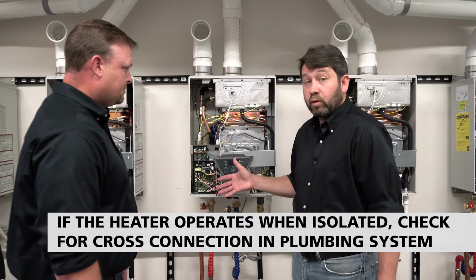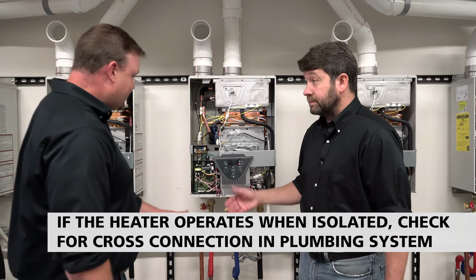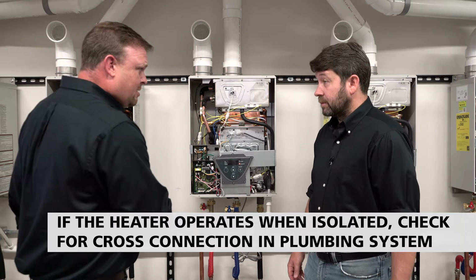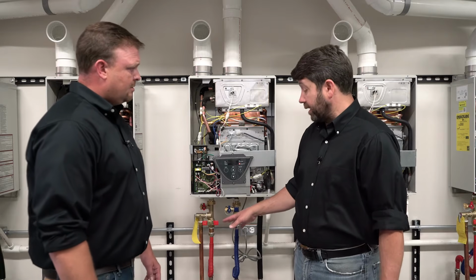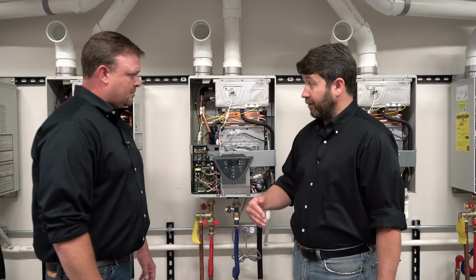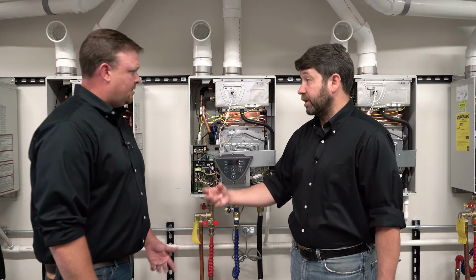And if it does come on and operate, then when we have flow, we know that the water heater is working correctly. Okay, and that could be just something downstream of the water heater? It could be something downstream, and what this does is this prevents any water from coming backwards through the water heater if we have a cross connection or we're missing a check valve.